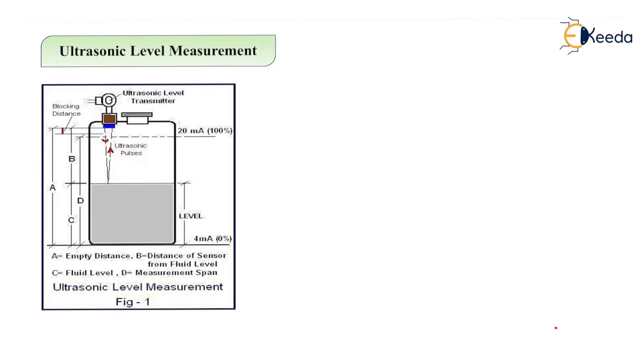Next is ultrasonic level measurement. In the diagram, the ultrasonic level transmitter is connected above the tank. There are four distances to be measured: distance A is from the bottom to the upper level — called the empty distance; distance B is the distance from the sensor to the fluid level; distance C is the fluid level; distance D is the measurement span; and the distance between A and B is called the blocking distance.